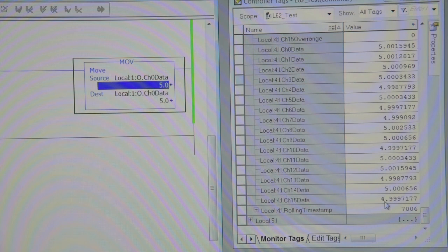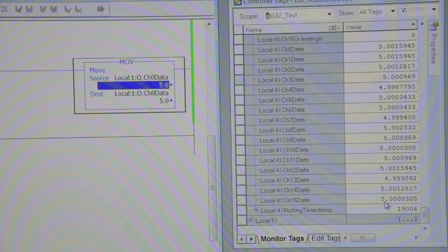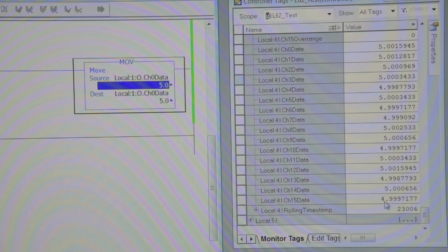So I'm quite happy with our output module being stable. So our inputs are all running between 4.998 and 5.002 at the most. So this module is fairly accurate. And like I say, we're doing a two second update so that everything's kind of smooth and we're seeing our numbers and being able to make sense of them.